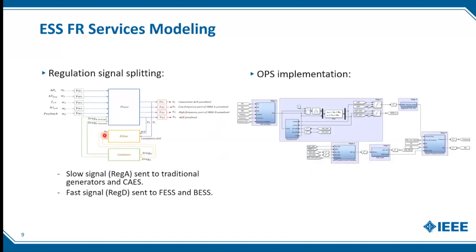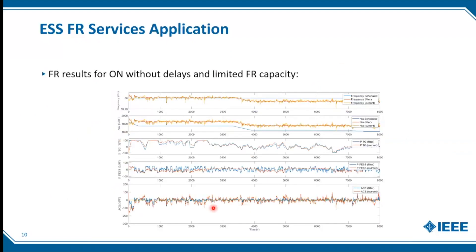One issue that had to be dealt with is communication delays. In actual power systems you can have significant communication delays when you send these signals. We advised the system operator that if you want to introduce energy storage services for frequency regulation, you first have to resolve the issue of communication delays. We developed, for the Independent Electricity System Operator of Ontario, a model and a control system that divides the frequency signal into two parts. What it shows is that as events happen in the system, the area control error, when you have these fast services, improves significantly.